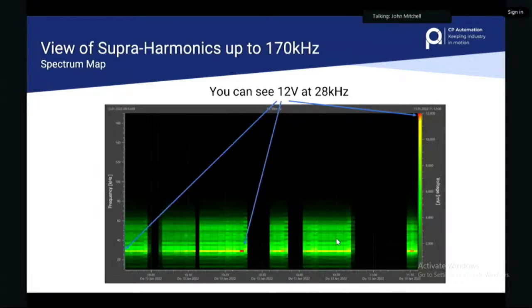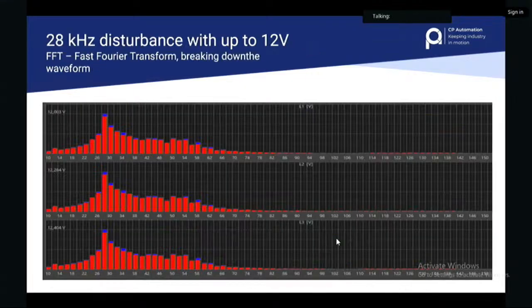In addition to that, we can create a thermal map. So I can see on a plant, if we do a measure for 7 days, which equipment is likely to be the problem with the frequencies that are being emitted. So, for example, electric vehicle chargers will be at a certain frequency band. Solar arrays will be at another frequency band. UPSs, another one. Variable speed drives, and so on. So I can see at what time of day, maybe it's during the daytime, and I see a frequency, you have solar on your site. And I can see that that frequency is getting above the limit. So a thermal map is a really good tool to be able to investigate, without knowing the entire site, what kind of equipment might be causing the problems they're seeing. From that, I can break down specifically the frequencies. I won't bore you with this today, it's in the presentation.